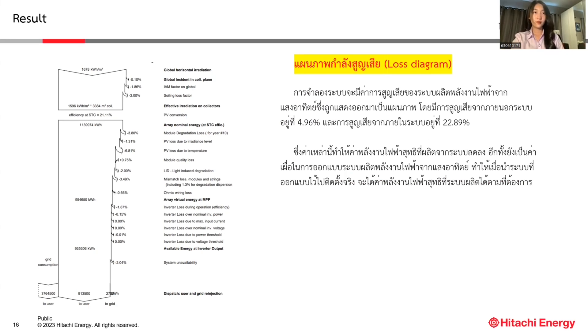Next is the power loss diagram, which shows that losses are broken down into two parts. External losses such as soiling and dirt on the panels account for 4.96%. Internal losses within the system — including losses in the cells, system components, and materials — total 22.89%. These losses determine the net energy production for the system.